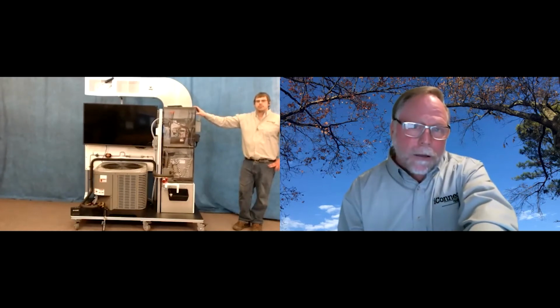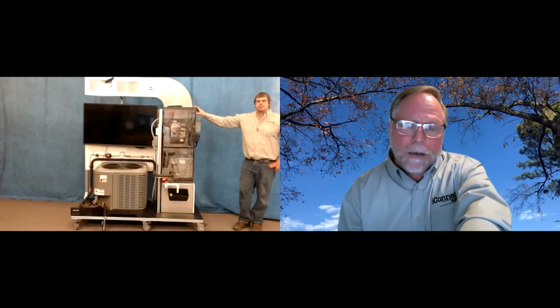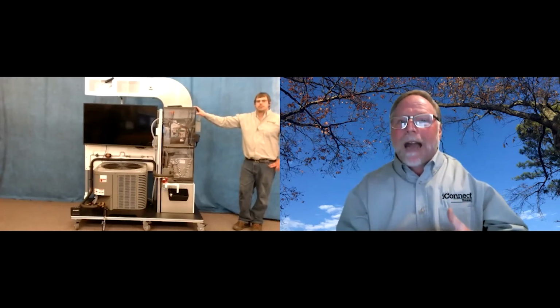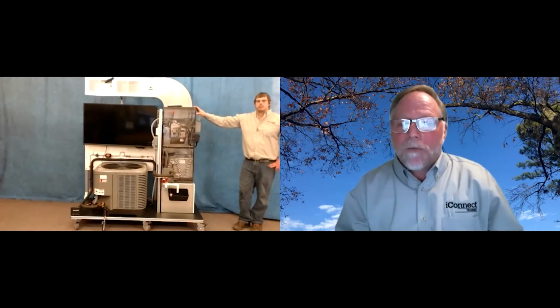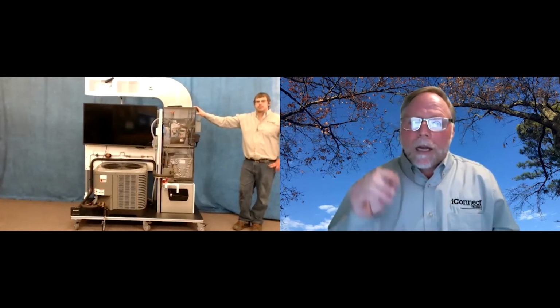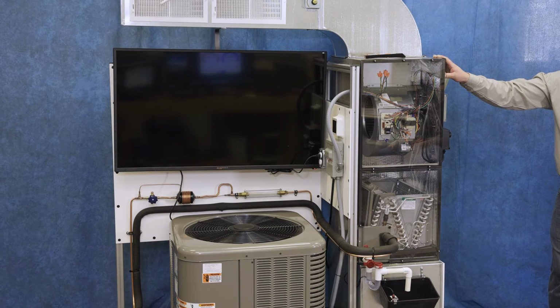Again, look at the superheat. See, the superheat staying very, very much the same because the expansion valve is metering back the refrigerant, trying to keep it from flooding that compressor. Eventually, it's going to get overcome, and we will start getting a lower superheat. Now, Nick, go ahead and change the filter and raise the airflow back up to normal.